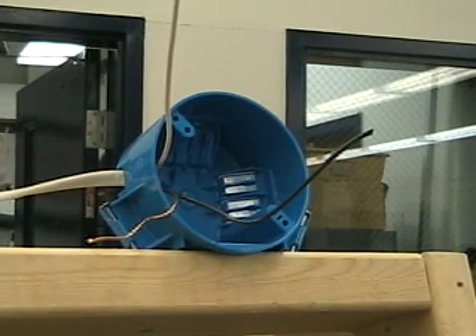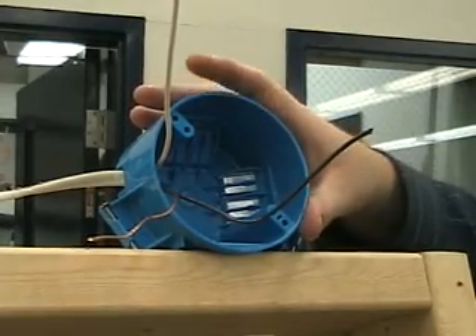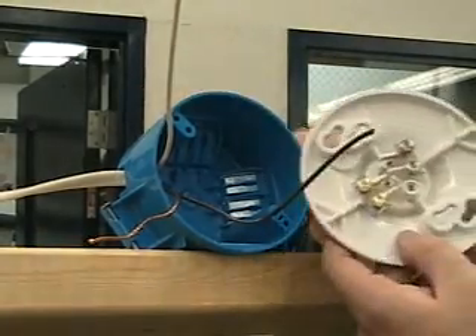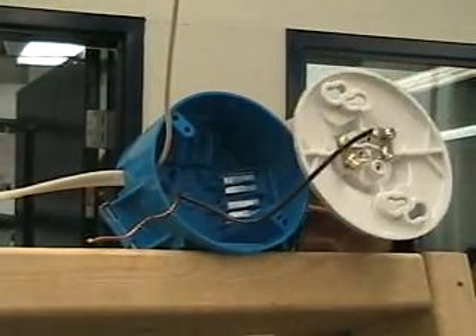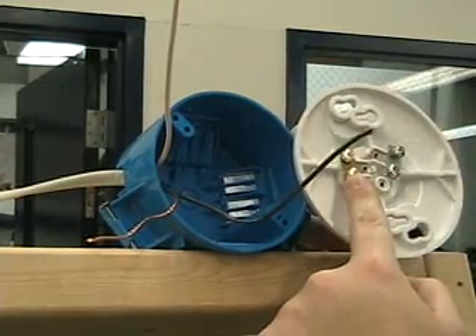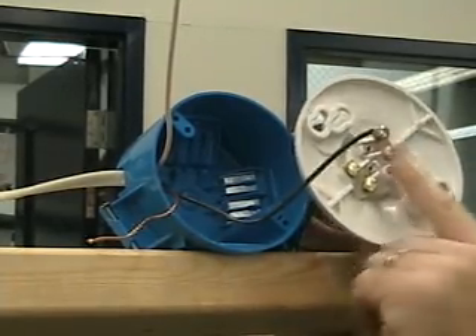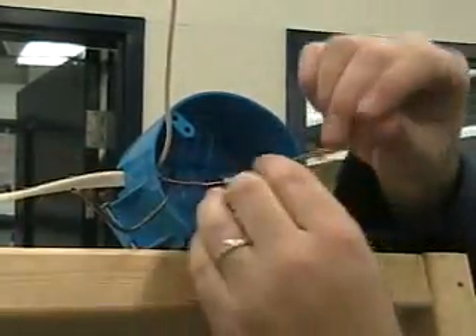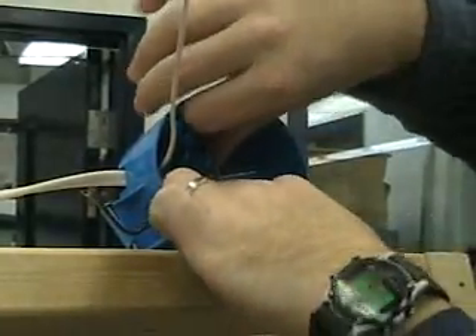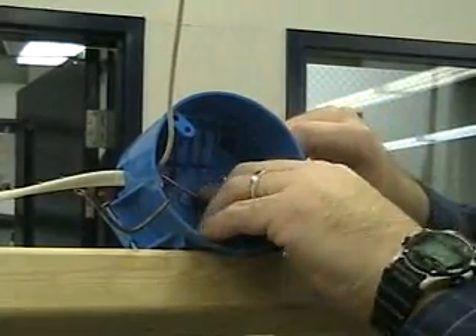The first thing you need to know about is this ground wire. Because this is a plastic box, you would normally put the ground wire on a grounding screw in here. Now this lamp holder happens to not have a grounding screw — it has gold screw terminals for your hot or black wire and silver ones for your neutral or white. So because this doesn't have a grounding screw, you're going to simply fold this very carefully into the back of the box, making sure you tuck it in very tightly.